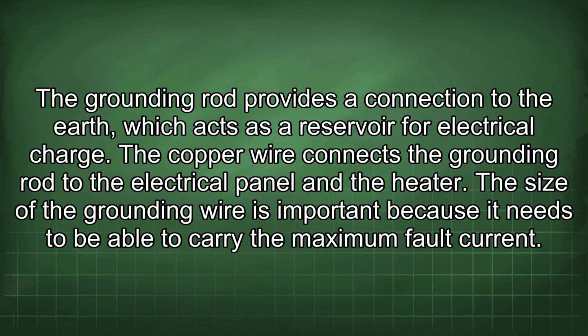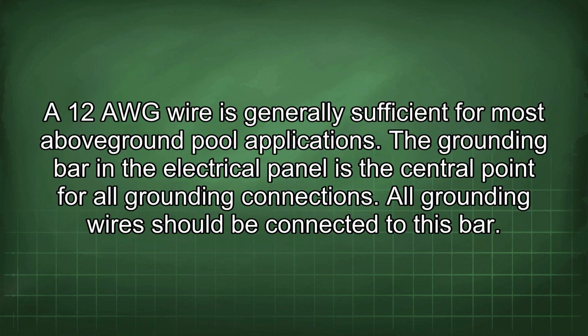The copper wire connects the grounding rod to the electrical panel and the heater. The size of the grounding wire is important because it needs to be able to carry the maximum fault current. A 12 AWG wire is generally sufficient for most aboveground pool applications. The grounding bar in the electrical panel is the central point for all grounding connections. All grounding wires should be connected to this bar.